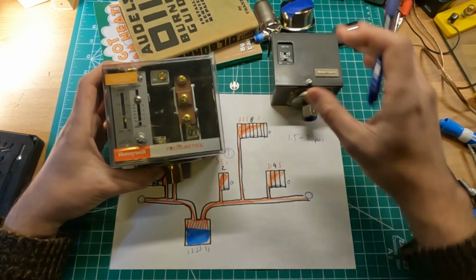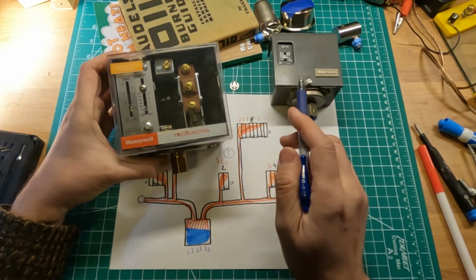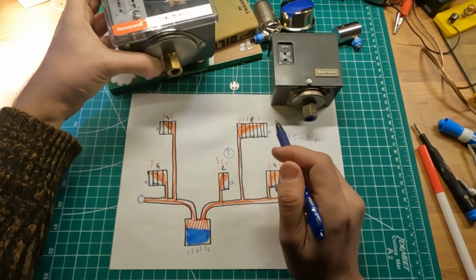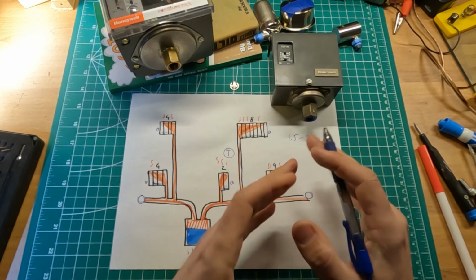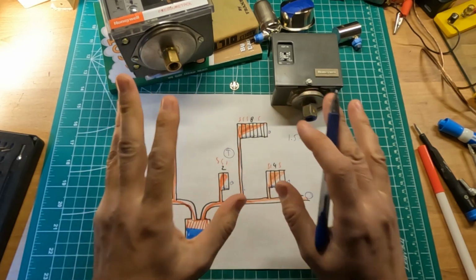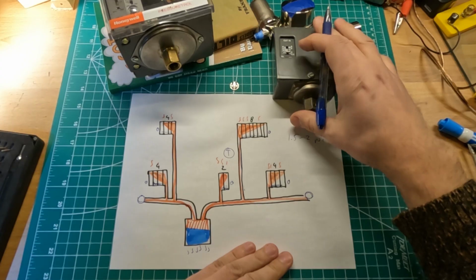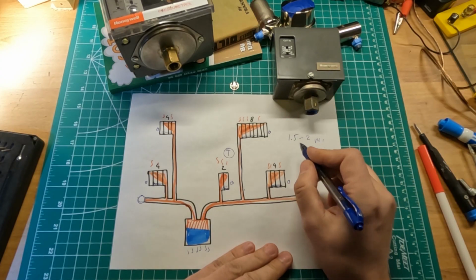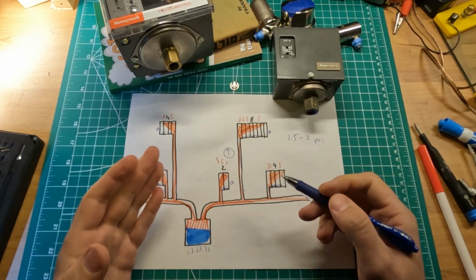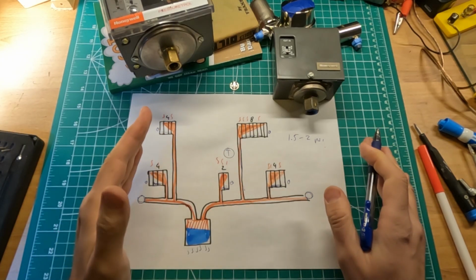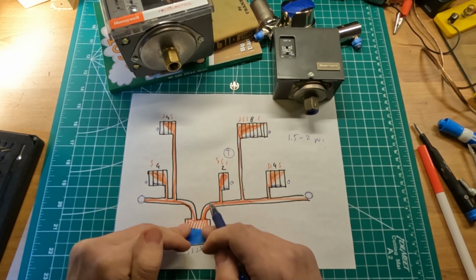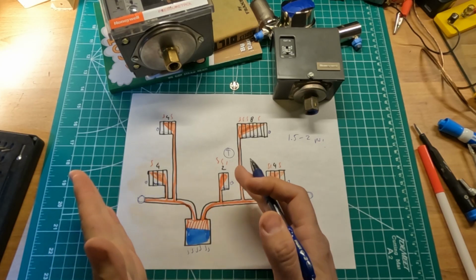So at such low pressure levels, 1.5 to 2 psi, those Pressuretrols are not particularly precise. Because of that, 1.5 to 2 psi is kind of a standard. It's low enough for those Pressuretrols to somehow be reliable, and it's still high to such an extent that you don't want to run your system at such high psi, partially because all of that psi is wasted steam. In other words, the steam builds up pressure inside the boiler, while that steam has at this moment nowhere else to go.